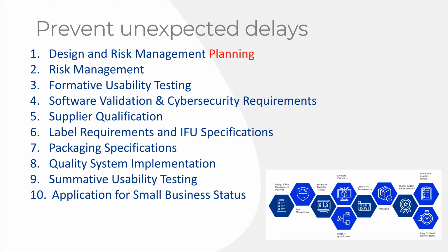That software validation document is a massive amount of documentation. It's 11 different documents that you have to provide, plus the off-the-shelf, plus the 2 cybersecurity. You're going to have a 1,000-page submission. Oh, but it got worse.